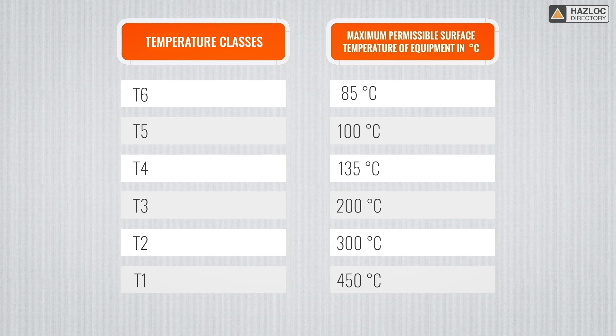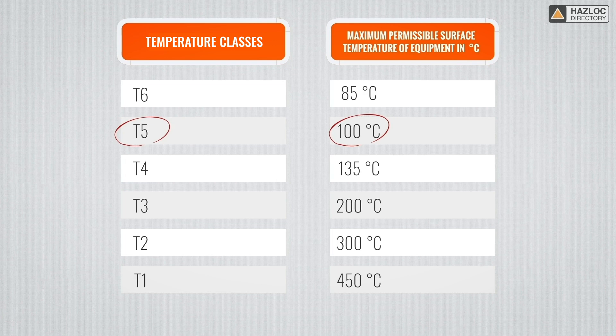What this table means is that a device classified as T5 will never attain a surface temperature higher than 100 degrees Celsius which can be exposed to explosive atmospheres and cause an explosion.